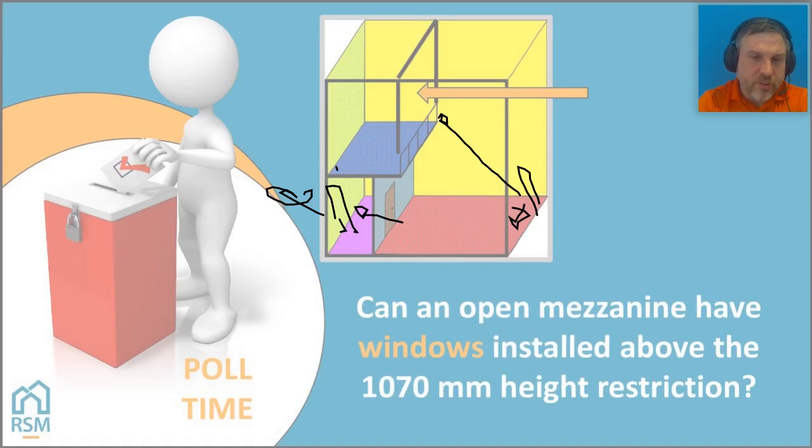With the new provisions brought in January, there are some provisions added for smoke dampers and smoke doors in certain situations, but none of those are specific to mezzanines that I know of. So it's strictly a fire separation or not. If it's a zero fire separation, a 0 hour fire resistance rating, that's inherently what it does, is stop smoke. I would just simply have it marked as an unrated fire separation on the plan.